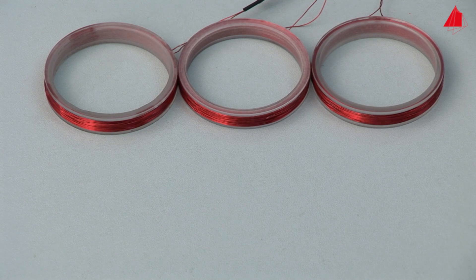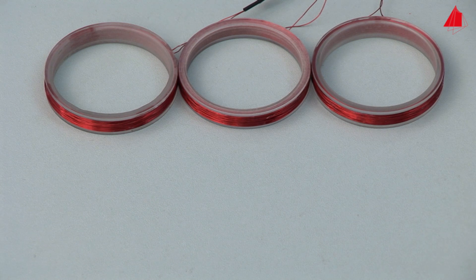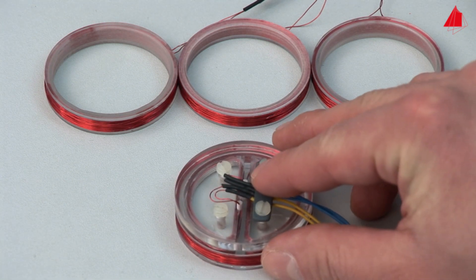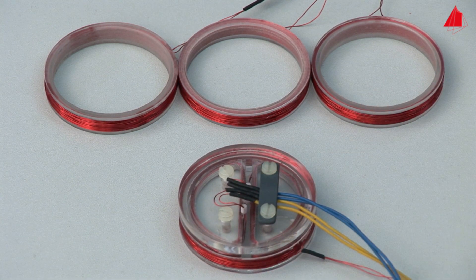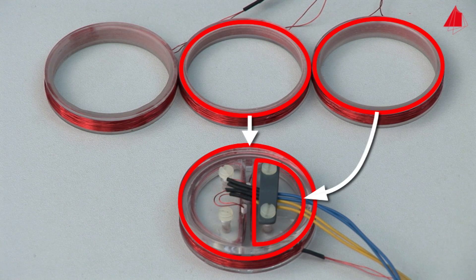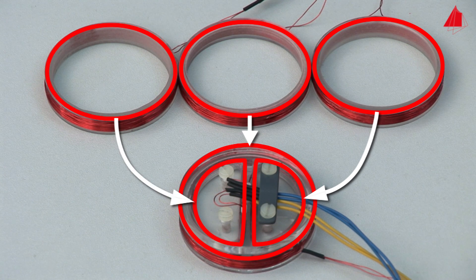Although the technique with adjacent coils seems impressive, it has disadvantages: the local resolution is not particularly good and very small defects are difficult to detect. A substantial improvement can be achieved with a different coil layout. The excitation coil remains unchanged; the right receiver coil is wound in the form of a capital D and sits within the excitation coil, while the left receiver coil is laterally inverted.